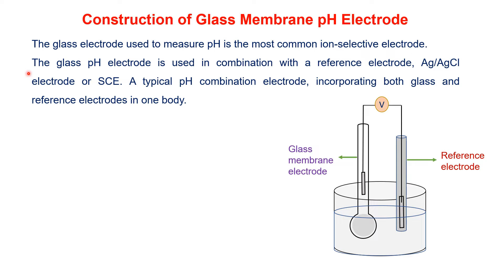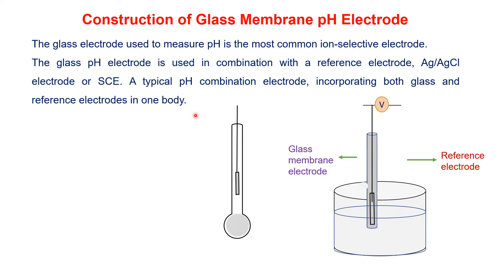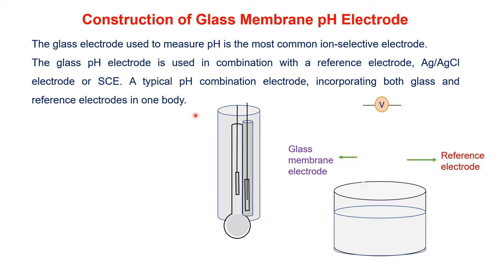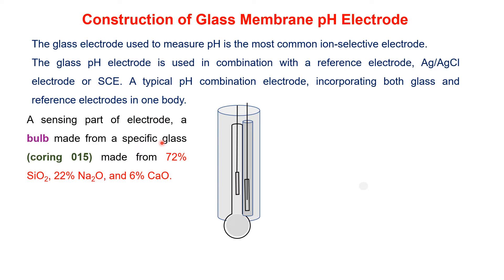The glass pH electrode is used in combination with a reference electrode. The reference electrode may be a silver-silver chloride electrode or a saturated calomel electrode. A typical pH combination electrode incorporates both the glass membrane electrode and the reference electrode in the same assembly — the modern glass combination electrode is an example of a tube inside a tube.